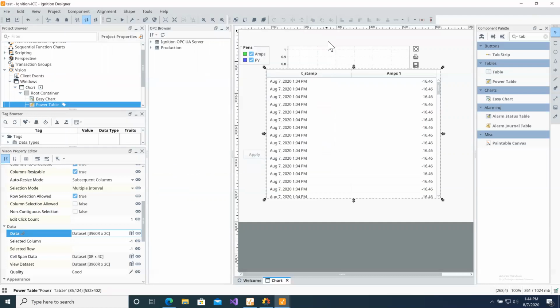Cool. The other thing is the MQTT data that you store. Can you also publish again from the Canary historian, or is it mostly just to store? In the newer version, they released version 20.2 about a week or two ago, and in that they did create the capability to push data out again out of the Canary historian to another MQTT broker. They added an MQTT transmitter into the version of the historian. So yes, you can push the data out again as well.